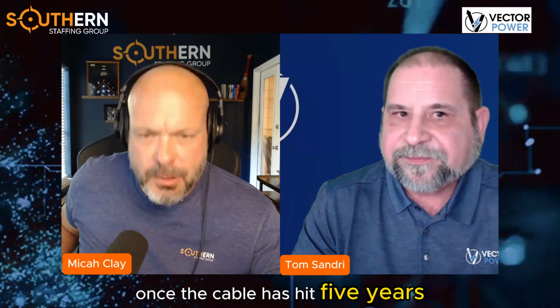So now what would constitute being service age cable? What's the typical life expectancy and when would that become a problem? In the IEEE guides and, well, almost all the literature now, we refer to service age once the cable has hit 5 years. Okay. Where did this number come from? Well, in the Insulated Conductor Committee, a lot of it was, and granted, take this with a little bit of grain of salt, because remember, in the Insulated Conductor Committee, a lot of the members and contributors come from the utility world.